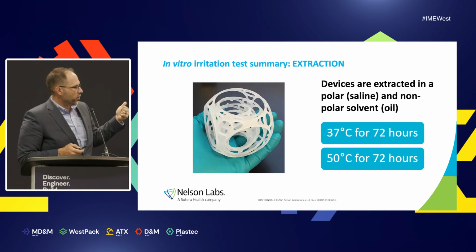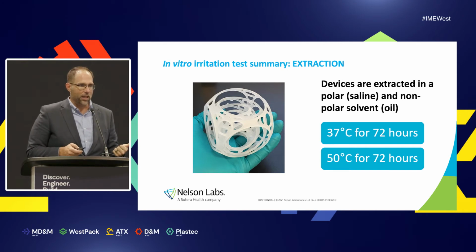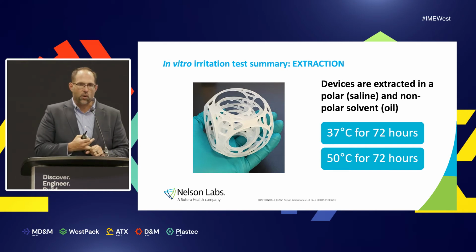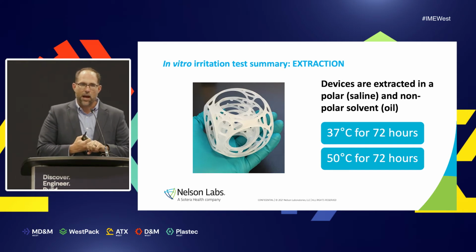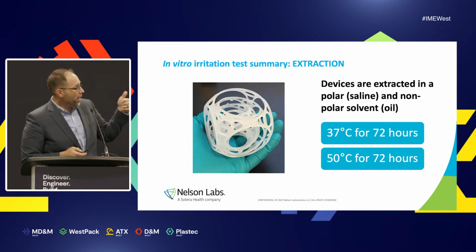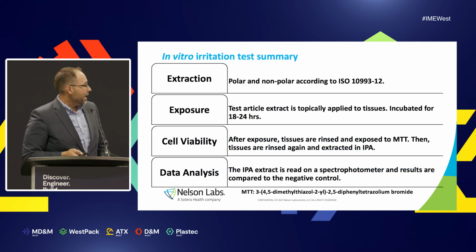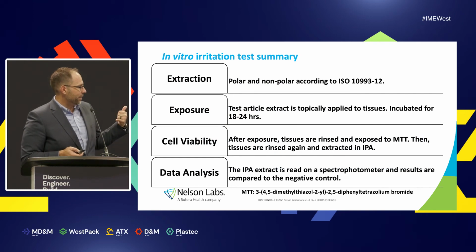The first one is extraction. We follow the exact same extraction procedure as the animal test. We extract at 37 degrees for 72 hours or 50 degrees for 72 hours based on the contact time of your device. We also still extract in saline and oil. So exactly like the animal test up to this point. The exposure is a little bit different.